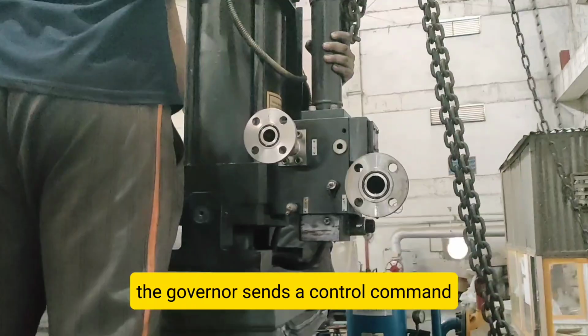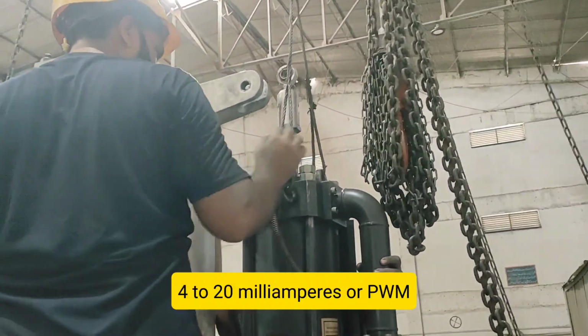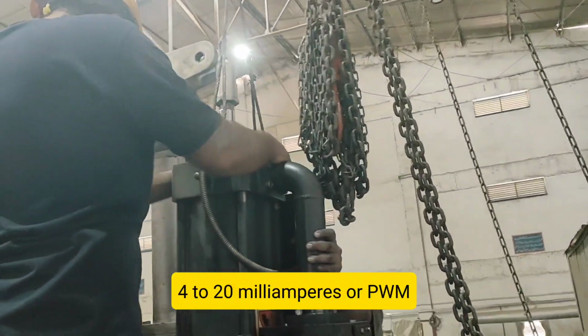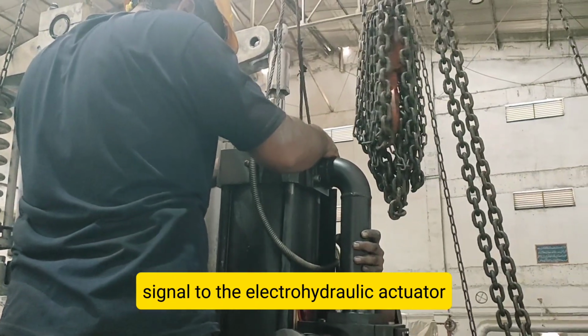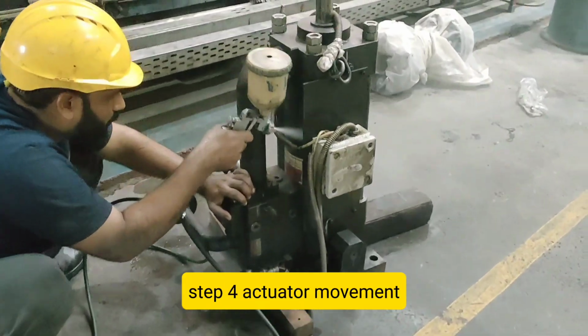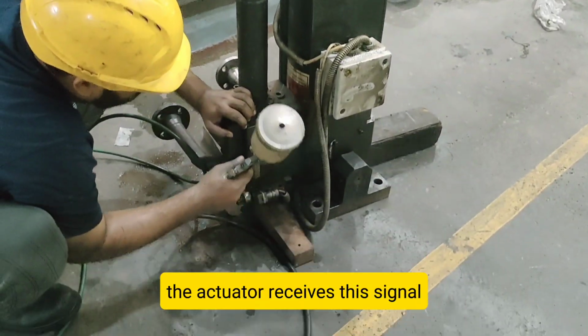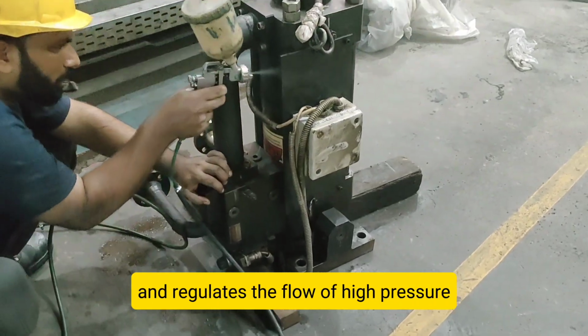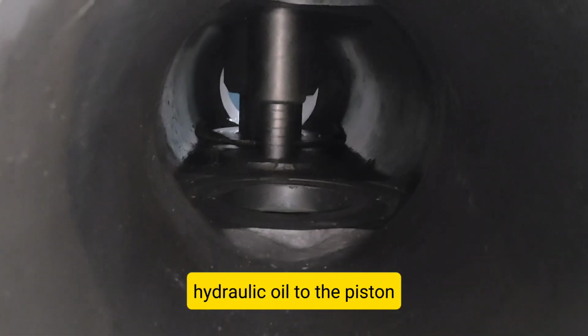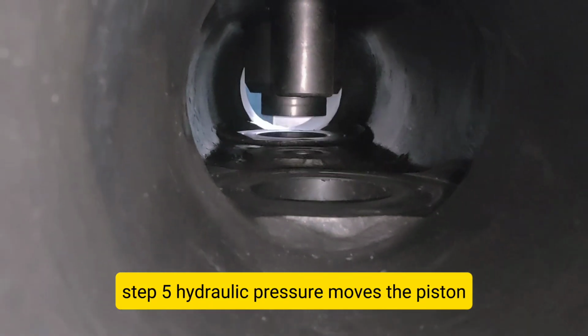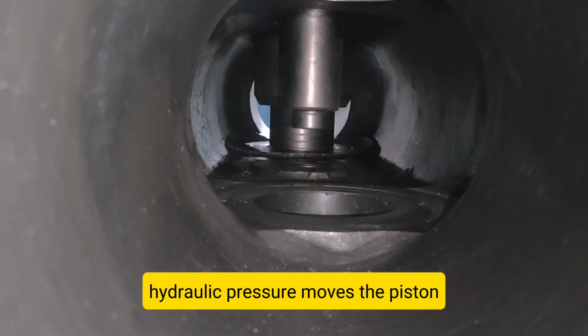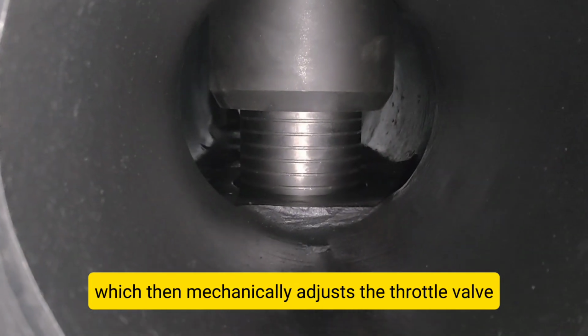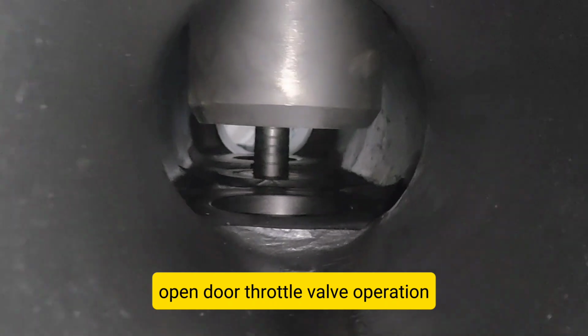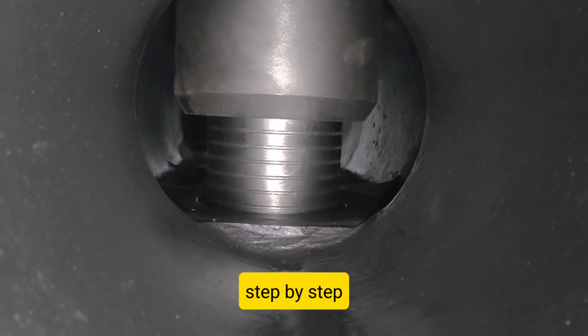Step 2. Speed and load matching. When there's a mismatch between actual RPM and set RPM, or when the electrical load changes, the 505 Governor calculates how much the throttle valve needs to open or close. Step 3. Command generation. The Governor sends a control command, 4 to 20 mA or PWM signal, to the electro-hydraulic actuator. Step 4. Actuator movement.